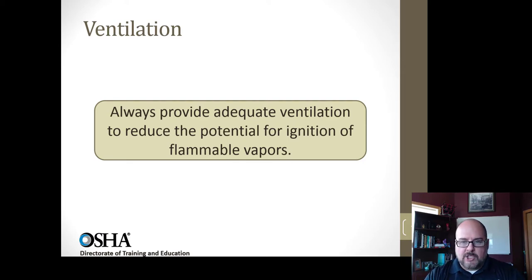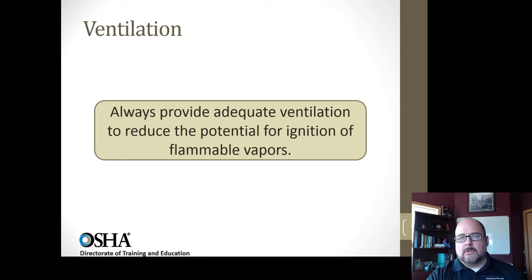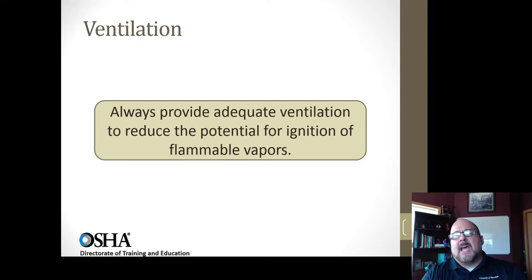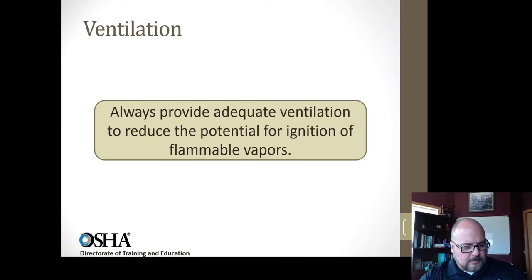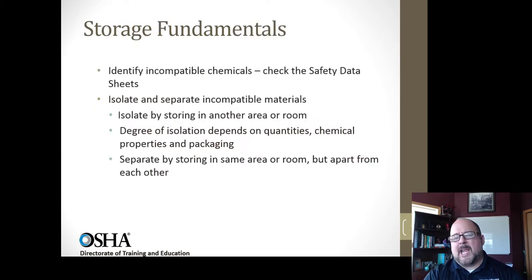Always provide adequate ventilation to reduce the potential for ignition of flammable vapors. Most flammable vapors have a density greater than air, so they tend to sink. For a flammable liquid ventilation system, you need an exhaust intake close to the floor — within about 12 inches — with cross-flow to collect and remove vapors from that point. Lighter gases like hydrogen are lighter than air and float upward. Carbon monoxide is near the density of air. Methane is also lighter than air. But flammable liquid vapors, typically chained carbons or petroleum distillates, tend to be heavier than air.